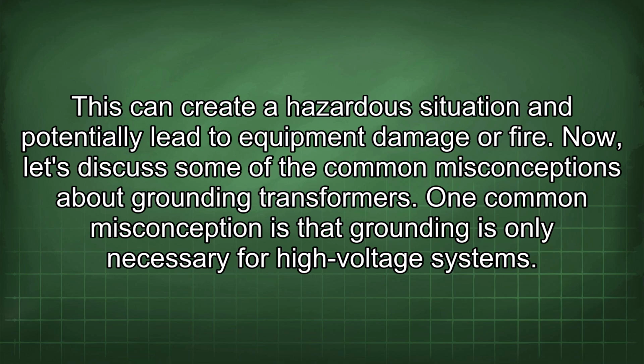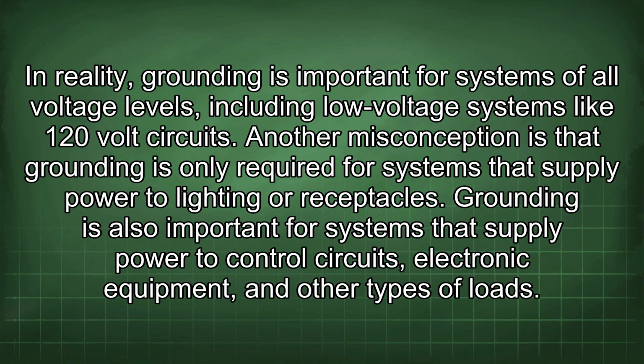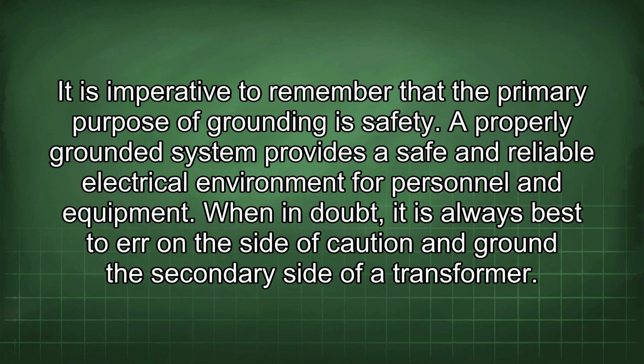Now, let's discuss some of the common misconceptions about grounding transformers. One common misconception is that grounding is only necessary for high-voltage systems. In reality, grounding is important for systems of all voltage levels, including low-voltage systems like 120-volt circuits. Another misconception is that grounding is only required for systems that supply power to lighting or receptacles. Grounding is also important for systems that supply power to control circuits, electronic equipment, and other types of loads. It is imperative to remember that the primary purpose of grounding is safety. A properly grounded system provides a safe and reliable electrical environment for personnel and equipment.